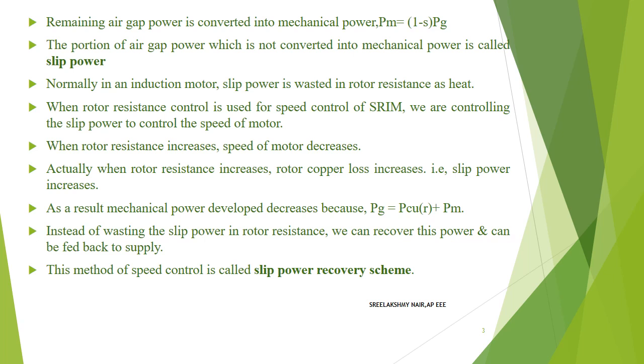When we use rotor resistance control, we control the slip power to control the speed of the motor. When rotor resistance increases, rotor copper loss increases — that is, slip power increases. As a result, mechanical power developed decreases, because PG equals rotor copper loss plus mechanical power developed PM. Instead of wasting the slip power in rotor resistance, we can recover this power and feed it back to the AC supply. This method of speed control is called slip power recovery scheme.